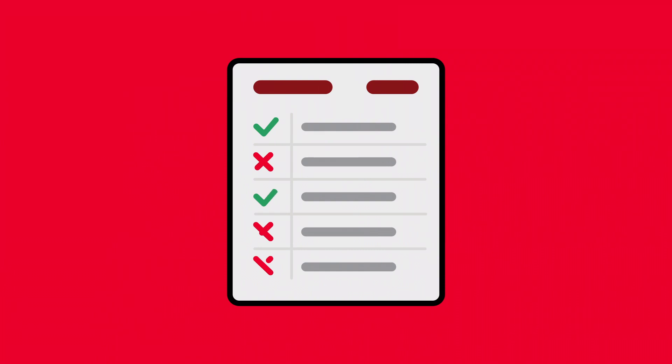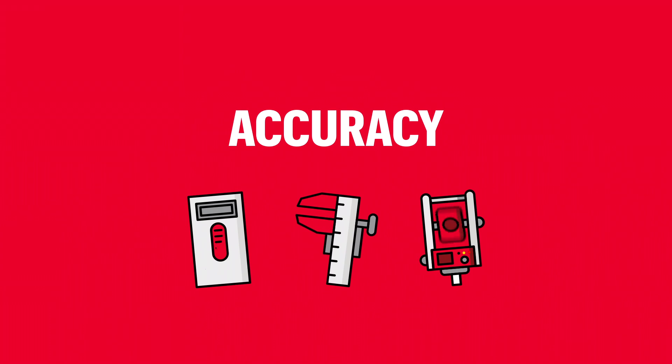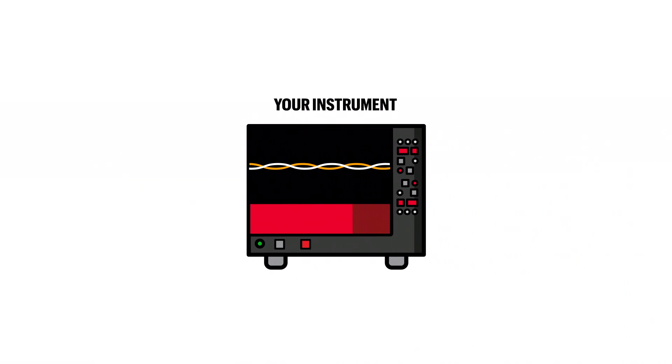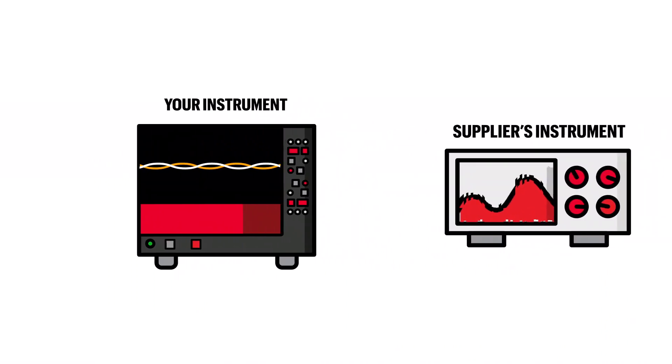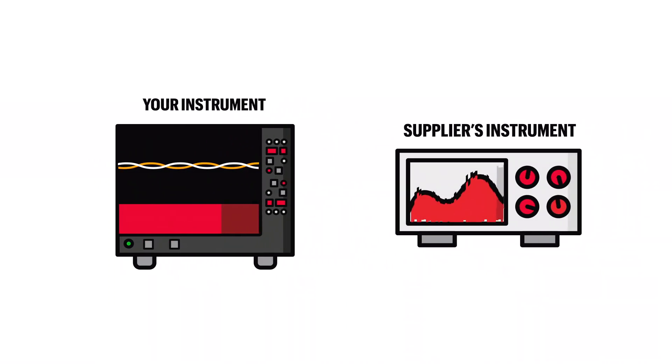Once your calibration supplier returns your instrument, how accurate will its measurements be? Does the supplier who calibrates your instrument use lab instruments that are more accurate than what you send them? Incredibly, not all of them do. In such a case, you cannot trust the accuracy of your instrument when it comes back from calibration.